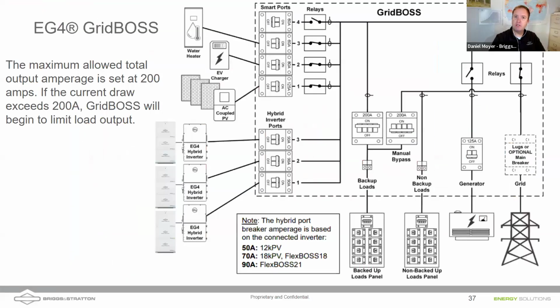That's the key with the Grid Boss. We have multiple inverters here. The combiner for L1 and L2 is in the Grid Boss, so we don't need anything external. We're able to feed the batteries to the individual inverters. The grid bypass is built into it, so we don't need an external bypass. We also have the ability to bring in a generator here with the 125 amp input, that's 30,000 watts. We don't need to combine it when we have multiple inverters, because it's all built into that Grid Boss.